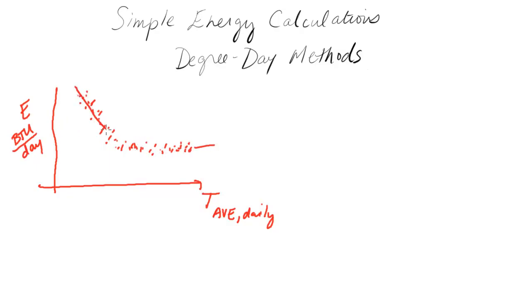And we also can now basically run a straight line through this. And we know that additional energy, we'll call this just EH for now. That's proportional to the difference of some parameter. Well, that difference, they found this to be typically around 65 degrees Fahrenheit in a variety of their cases. And so if we want to know what the difference is at any point, that's going to be 65 minus your temperature.